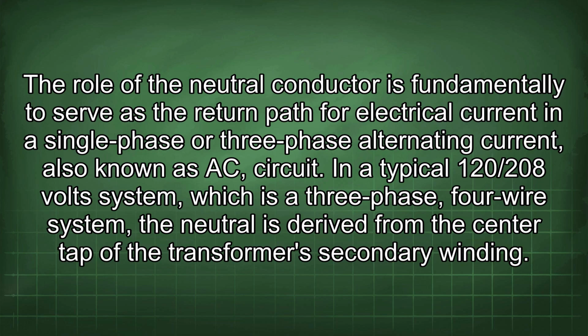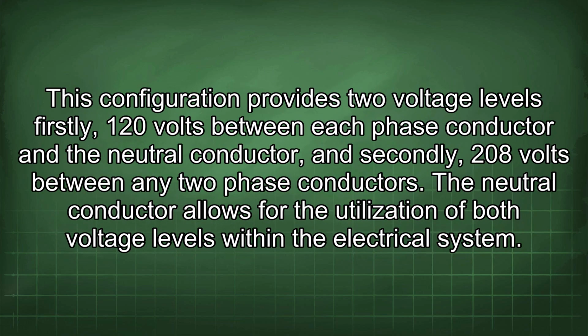120/208 volt system, which is a three-phase, four-wire system, the neutral is derived from the center tap of the transformer's secondary winding. This configuration provides two voltage levels: firstly 120 volts between each phase conductor and the neutral conductor, and secondly 208 volts between any two phase conductors. The neutral conductor allows for the utilization of both voltage levels within the electrical system.